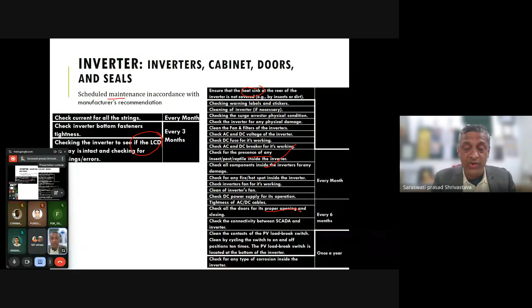AC/DC cables need proper opening and closing, because what we found is pigeons made their nests there, and you will find some rats as well. So we have to check this and get it covered so there shouldn't be any space, otherwise there will be a short circuit. SCADA check every 6 months, and the PV load breaker and corrosion check once a year. These are simple things from the electrical side point of view.